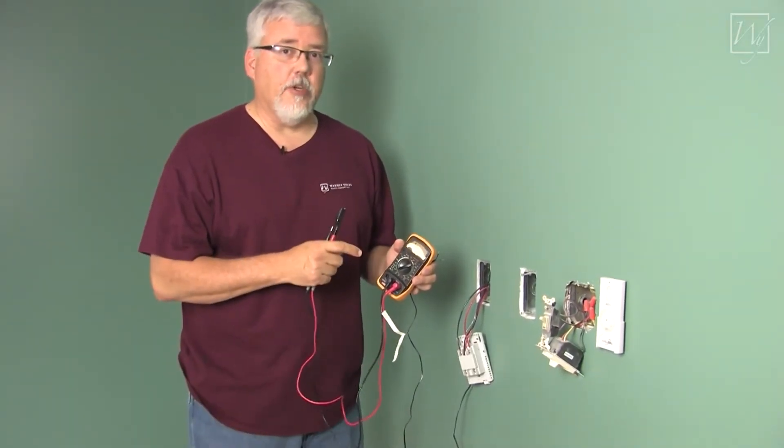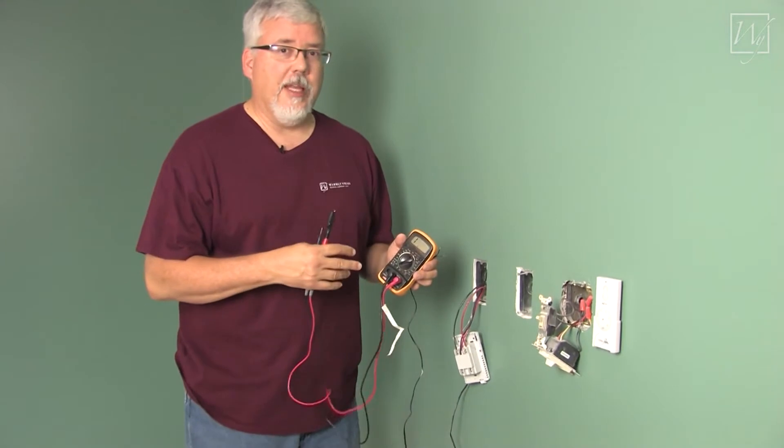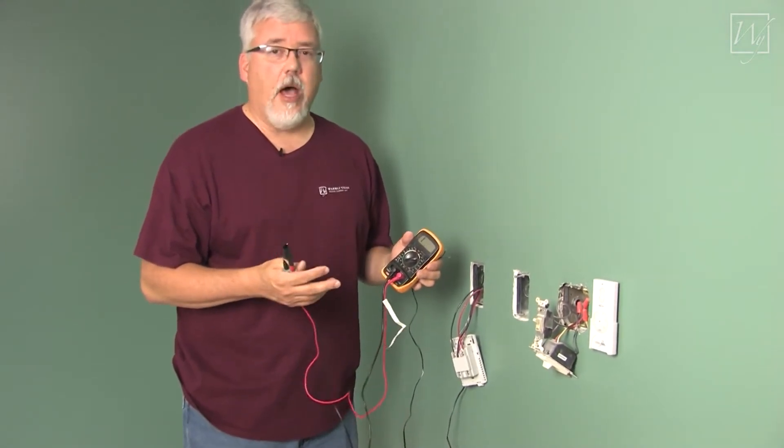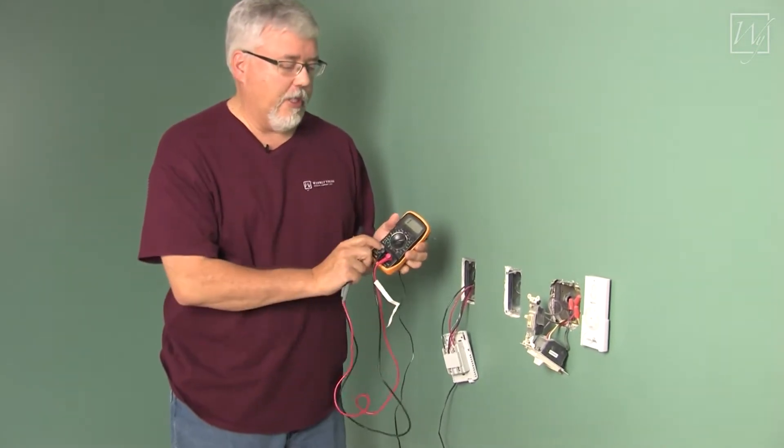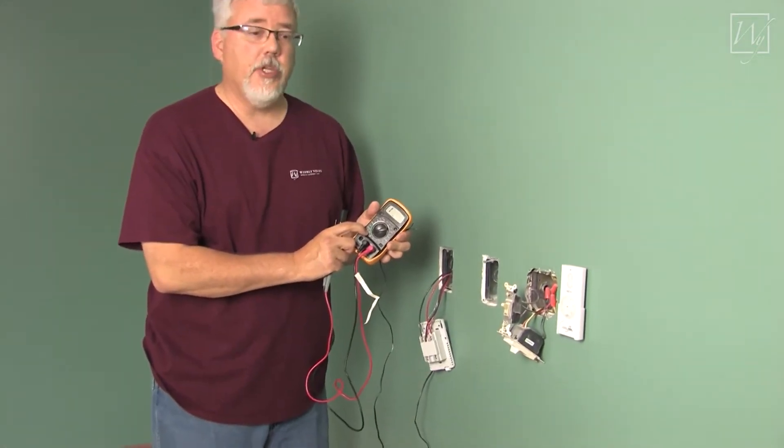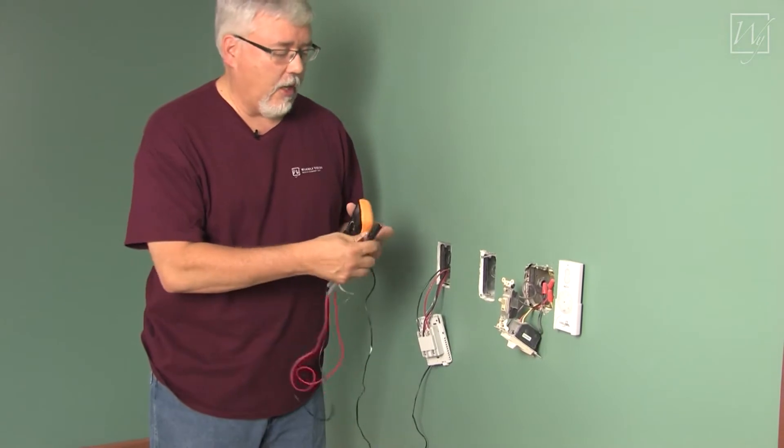Now we're going to take our thermostat sensor and test it to make sure it's good. It's going to read anywhere between 8,000 to 18,000, somewhere in there, just depending on the temperature of the room itself. We need to set to the 20k range, and that's where we're going to make our readings.